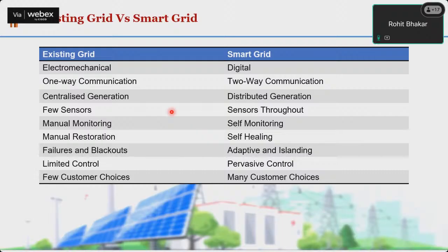Earlier, we used to have manual restoration in case of any fault. Now healing happens on a self-contained basis: the system itself operates the reclosers and circuit breakers such that self-healing is made possible. Failures and blackouts were a common feature before. Now, instead of failures and blackouts, we are shifting our strategy so that adaptive healing or islanding is possible for those power systems.